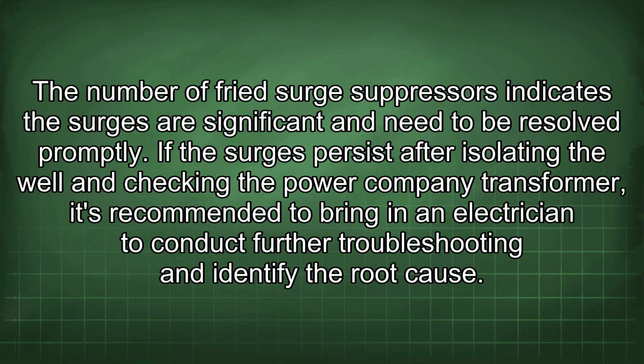The fact that the surges are occurring randomly suggests they are not caused by a specific appliance or circuit. The number of fried surge suppressors indicates the surges are significant and need to be resolved promptly. If the surges persist after isolating the well and checking the power company transformer, it's recommended to bring in an electrician to conduct further troubleshooting and identify the root cause.